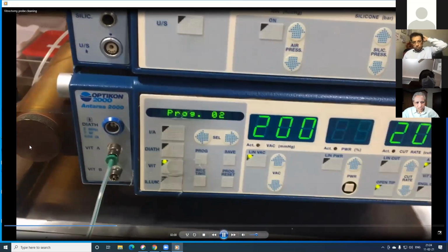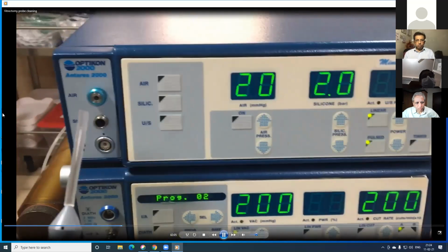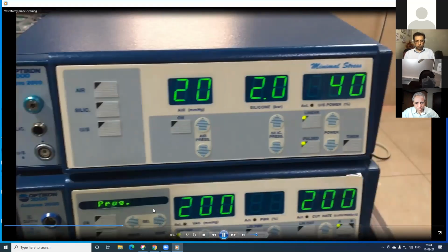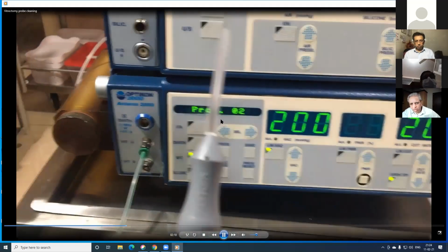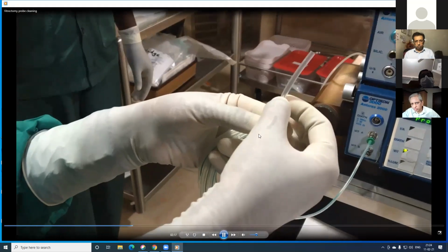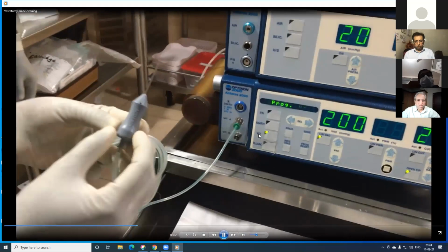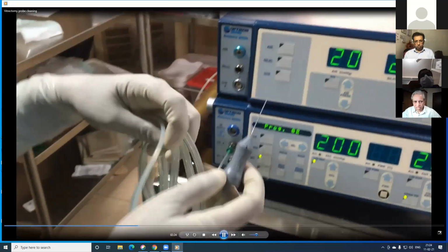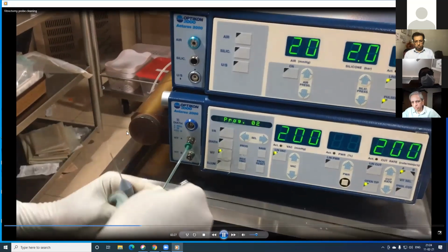And that is always kept covered with a silicon tube, which is open on the other end. As you can see, that's a probe. That's a vitrectomy by Mid-Lab. And we write A, B, C on it, depending upon the end of surgery. If it's a good cutter still, we're going to reuse it. We can use it for 4 to 5 vitrectomies. If you have used it to chop the lens, then its life is much lesser. But if you are using it only to cut the vitreous, then its life will be longer.